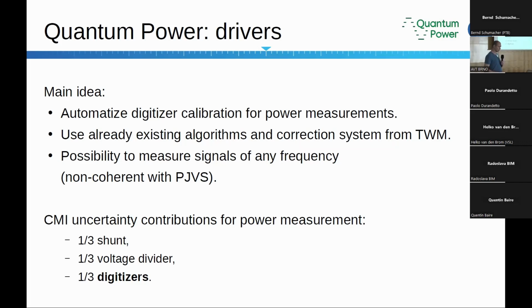There is also such a possibility that the Josephson, at least my Josephson, has a problem that I cannot measure any frequency I want. Because if I use differential measurement, then the Josephson must be coherent to the source or to the measured signal. And thus I cannot make a coherence for any frequency, just only some set of frequencies. But using this system, we can rely on the digitizer if the gain of the digitizer is not changing much with frequency, or at least in some small range. We can measure any source of any frequency using the Josephson.